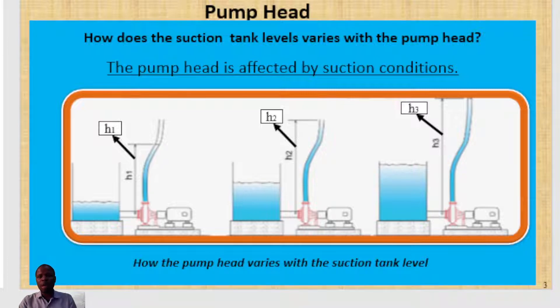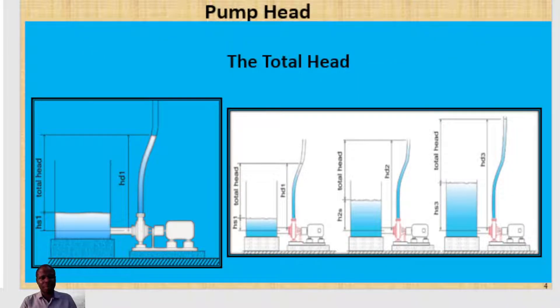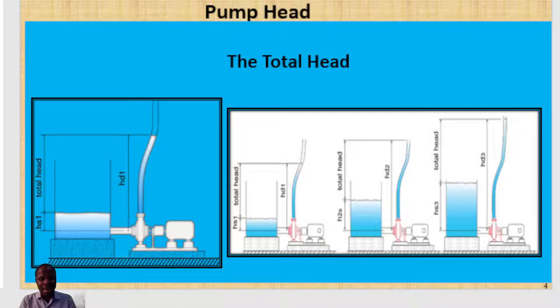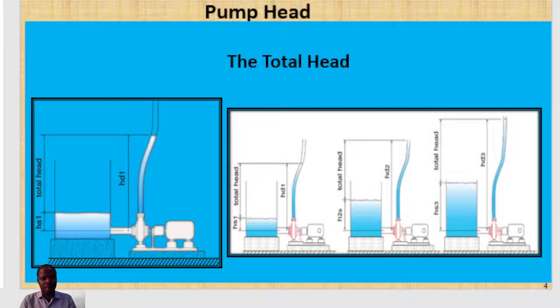Now you also need to know another concept, which is called the total head. A much more useful measure of head is the difference between the liquid level in the suction tank and the head in the vertical discharge pipe. That difference in liquid level at your discharge end of the pump and what you have at the suction tank level is what is referred to as the total head that the pump can produce.